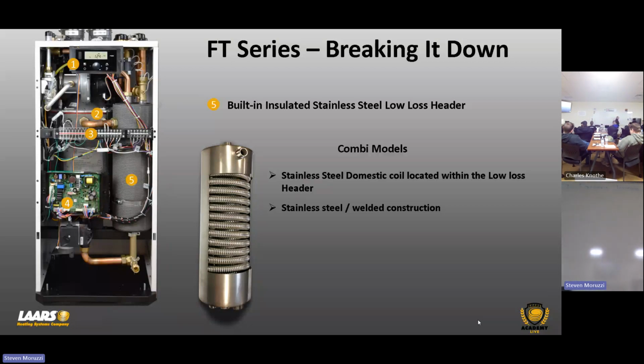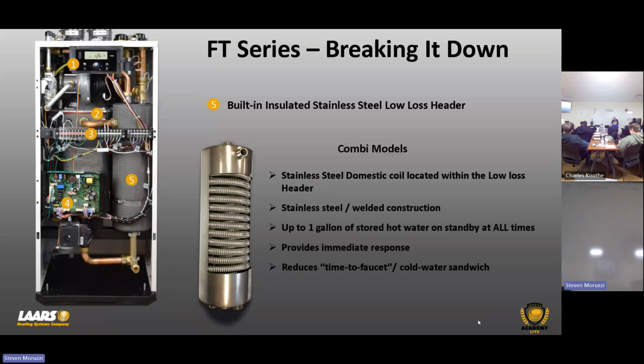So on the floor model, again, it's all stainless steel welded. We're always in tank charge mode. So the flow for this, even on a heating demand, I'm sending heat out. So here's my heat exchanger. Here's my pump. I'm flowing from the low loss header through the primary heat exchanger and back. So that's what it's doing. Again, I'm always in tank charge mode. My system is being drawn off the top with system pumping. Does that make sense? Okay.